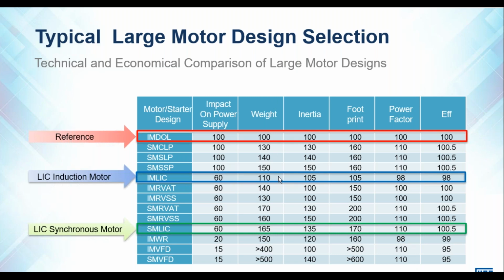The weight is slightly more because we need more active material in order to decrease the current, basically to increase the reactances. The inertia is slightly higher because of that additional material. Our footprint is slightly higher, but very similar. And the power factor and efficiency is slightly less, but very, very similar. And then I've just highlighted the same comparison for a low inrush current synchronous motor.